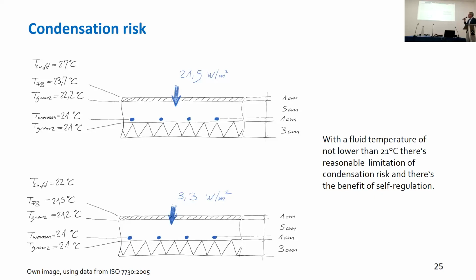Talking building physics, looking at temperature levels, starting with a room of 27, summer situation up there, having pipes operated at 21 degrees, then you will find temperatures like this. And at least in our region, there will be no condensation risks. As soon as you start to operate the pipes with crazy 16 and 18 degrees, you will have a condensation risk in the floor. You will have condensation risks for wooden floors, and it's really dangerous, because you don't see it for years, but you will smell it then, and it's really a problem.